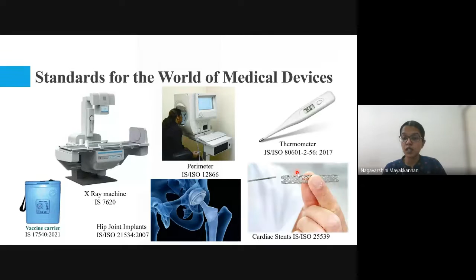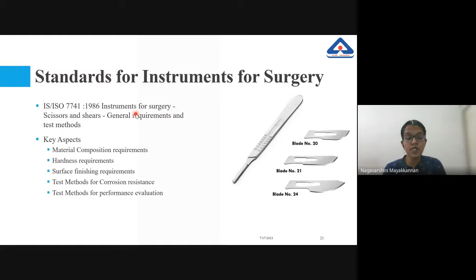So we have standards for various categories of medical devices which are used in the medical world. To be specific, we have standards for surgical instruments. The standard ISO 7741 is for instruments which are used in surgeries. The key aspects of the standard include requirements for material composition, hardness, surface requirements, corrosion resistance, the test methods used to determine whether a particular product is resistant to corrosion or not, and performance evaluation, like the efficiency of the blade of the knife or the scissors used in surgical procedures. All these test methods, material composition requirements, and hardness requirements are specified in this standard.